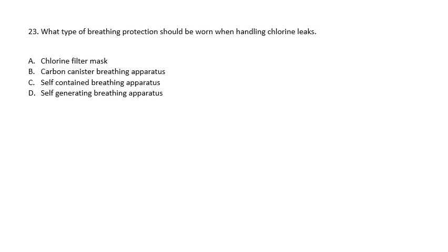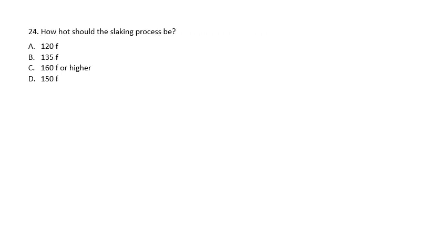What type of breathing protection should be worn when handling chlorine leaks? A chlorine filter mask, a carbon canister breathing apparatus, self-contained breathing apparatus, or self-generating breathing apparatus? The answer is self-contained breathing apparatus. How hot should the slaking process be? 120 degrees Fahrenheit, 135 degrees Fahrenheit, 160 degrees Fahrenheit or higher, or 150 degrees Fahrenheit? The answer is 160 degrees Fahrenheit or higher.